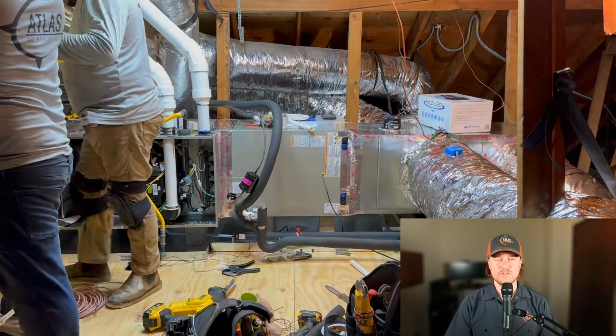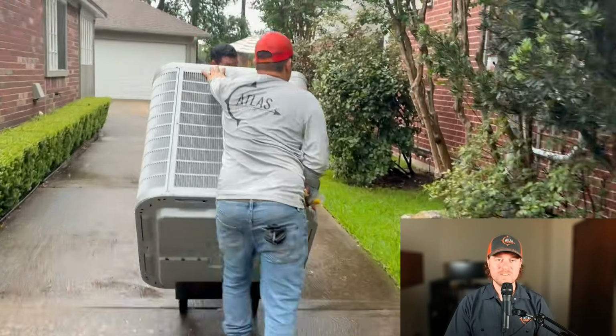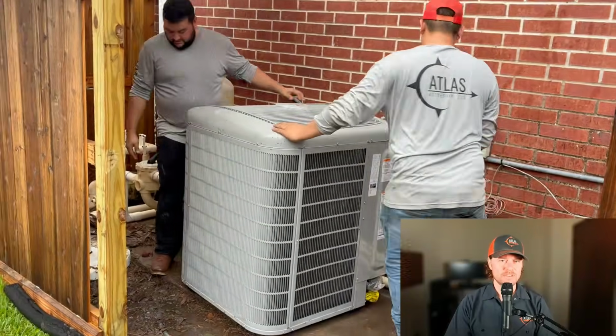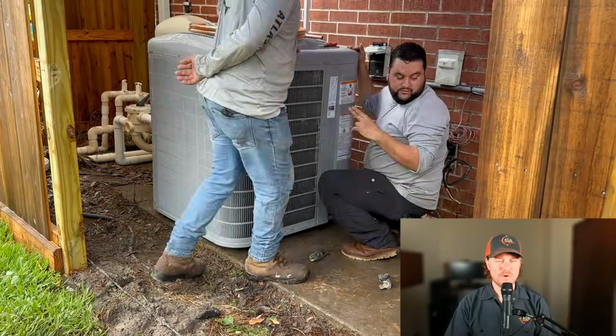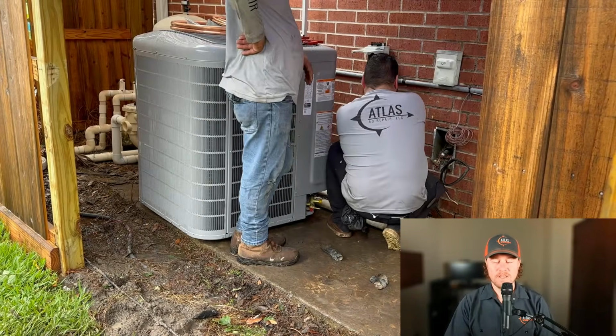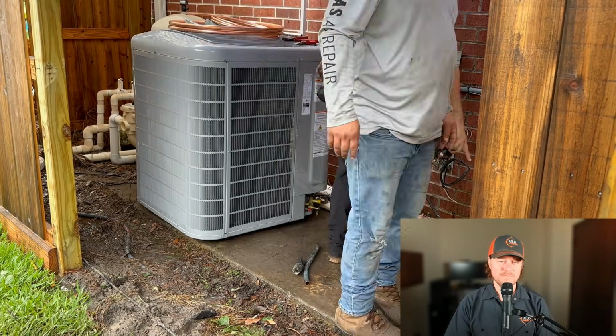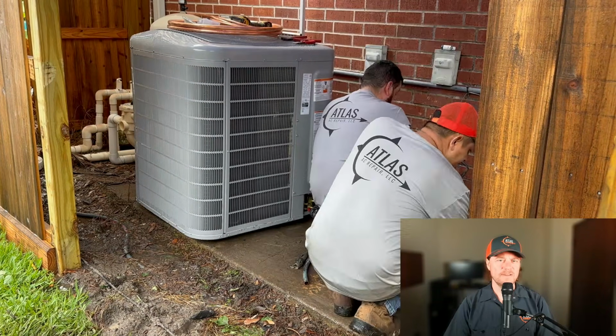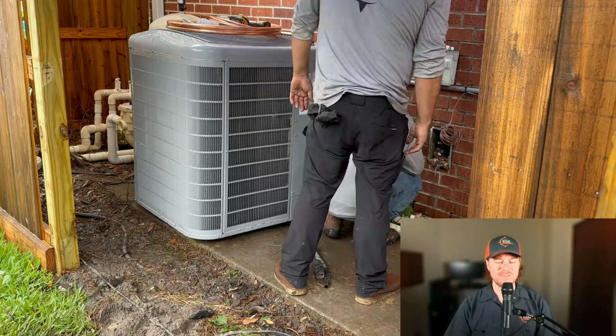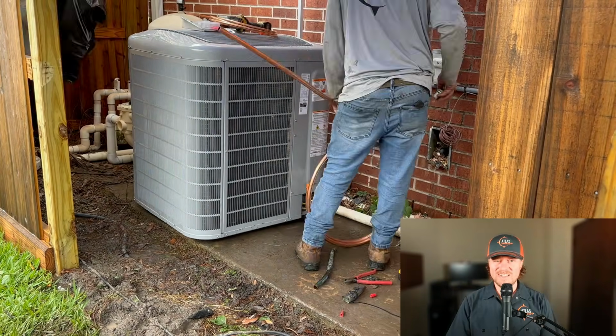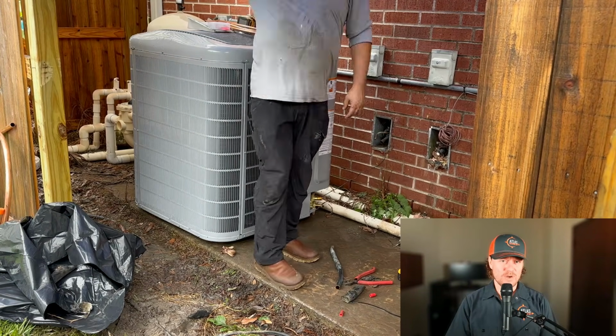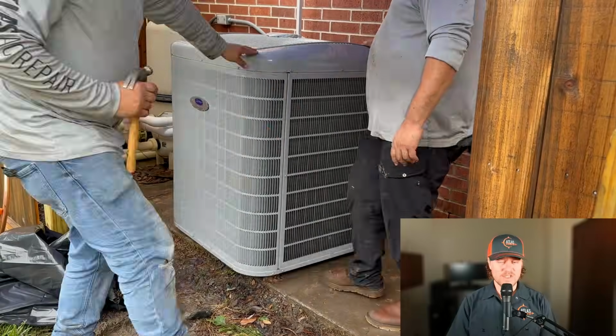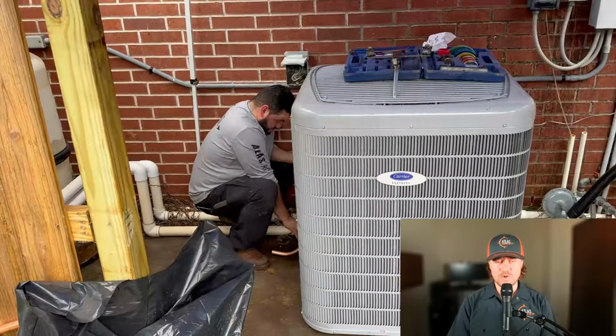And that's one of the issues whenever you do duct modifications. Realistically, to get close to identical temperatures in every single room, you would need to run a heat load per room, do a manual D takeoff, and replace all your ductwork. And that costs a lot of money. And lastly, to say that my house is balanced out for non-zoning is kind of disingenuous. You see, it is technically balanced out in cooling mode, but not in heating mode at all. And it's going to end up overheating the upstairs when winter rolls around.